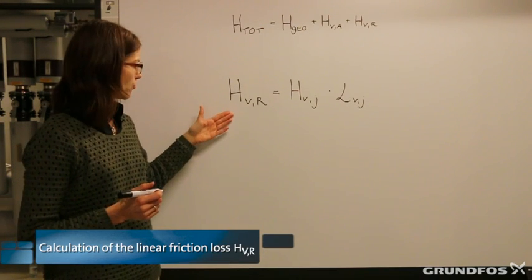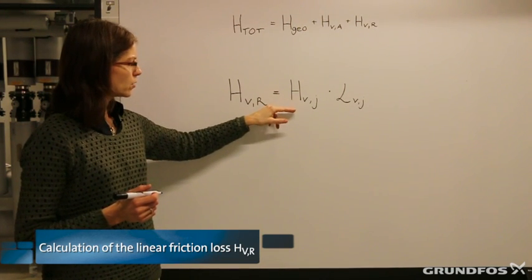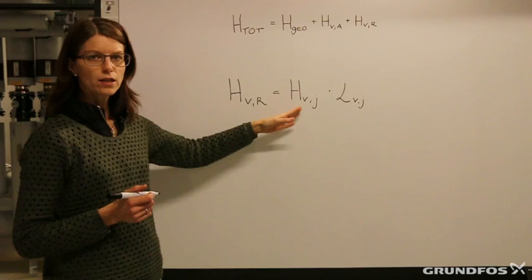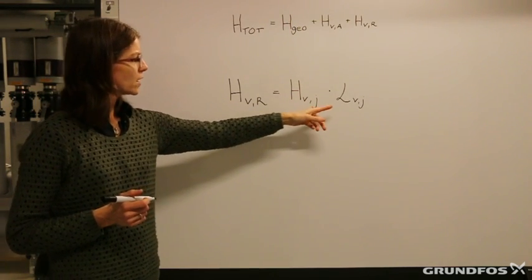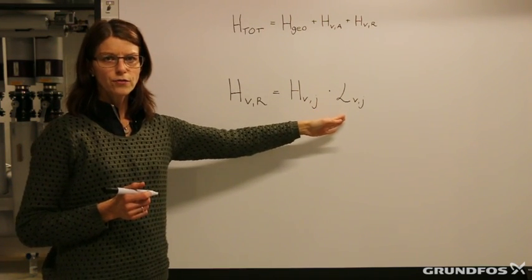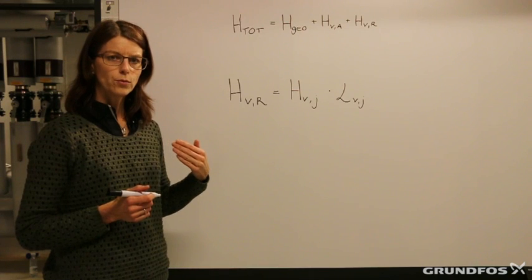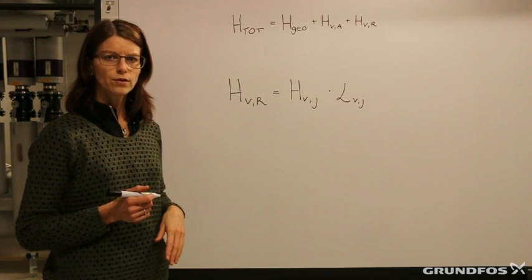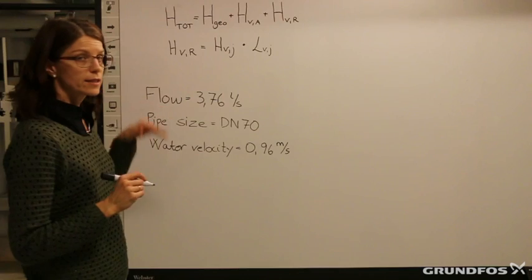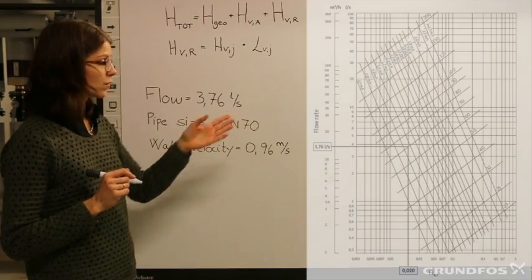Now we have the formula for the pressure loss in the linear pipe system. It's the pressure loss dependent on the flow rate — a value we can find in a chart — multiplied by the length of the pipe. It's important that we only choose the length of the upward-going pipe, because the wastewater in the downward-going pipe is moved by gravitation. For the calculation of the friction loss in the linear pipe, we need to use a diagram.